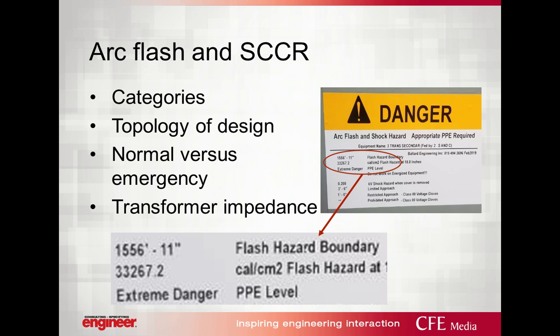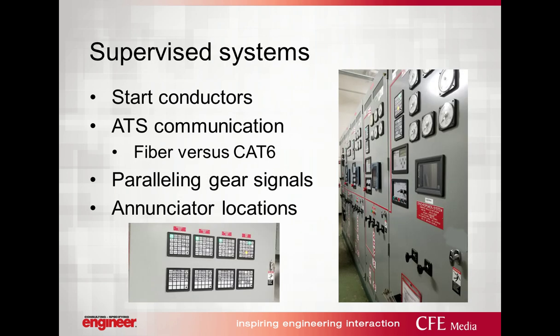Now, when we're doing these calculations, I do a comical example here. This is a sticker on a piece of gear, and the result of this calculation was because they didn't take into consideration primary fusing on a large transformer. So obviously, a flash boundary of 1,556 feet isn't necessarily very useful, but we want to take that into consideration when we're doing these calcs. Remember that it's still software, and whatever information we put in is going to determine what kind of information that we get out.